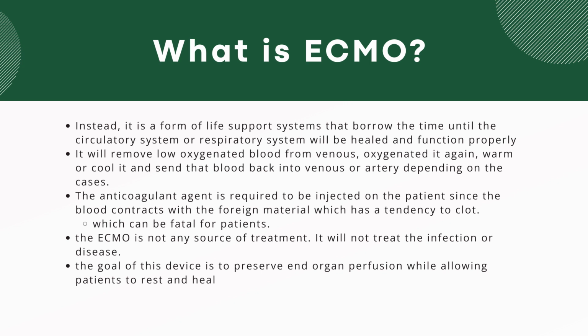As for its mechanism, it removes low-oxygenated blood from the venous system, oxygenates it again, warms or cools it, and sends it back to the venous system or artery depending on the case. In addition, an anticoagulant agent, the substance that prevents blood clotting, is required to be injected into the patient since the blood here contacts foreign material, in this case, the circuit. We have the pump, we have the oxygenator, which has a tendency to clot. And these blood clots can be fatal for the patient if not controlled. So basically, this device's objective is to preserve end organ perfusion.